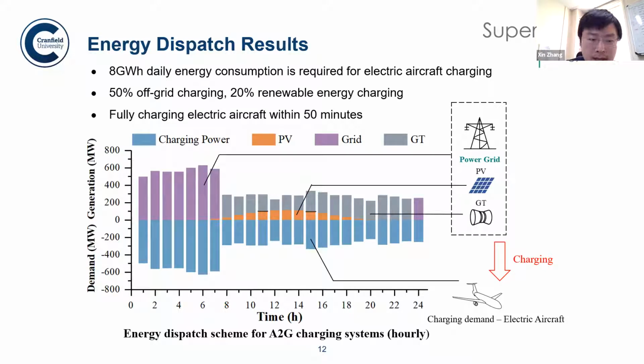As you can see, from midnight to about 7 a.m. in the early morning, all the charging demand is met by the power grid, because electricity prices are very low during the night. That's why our energy dispatch strategy buys all electricity from the power grid for electric aircraft charging at that time. During the daytime, because the grid may already be at full capacity, we use the on-site gas turbine within the airport to meet the charging demand.